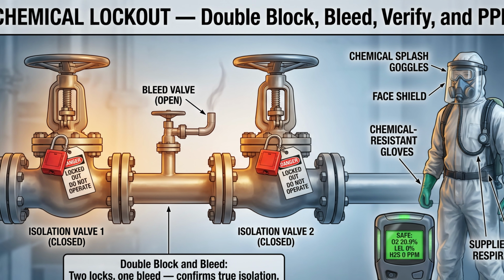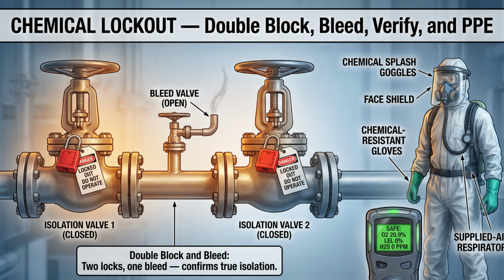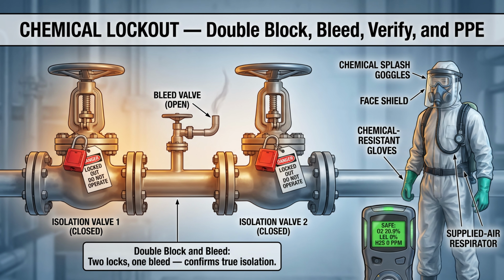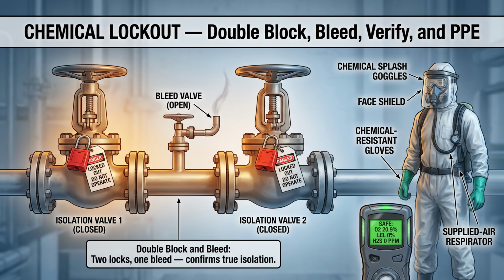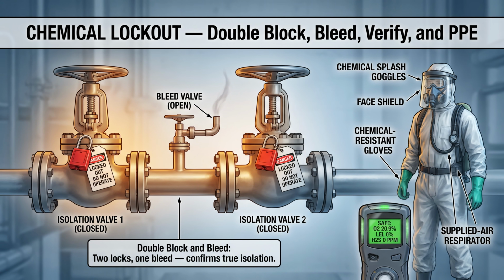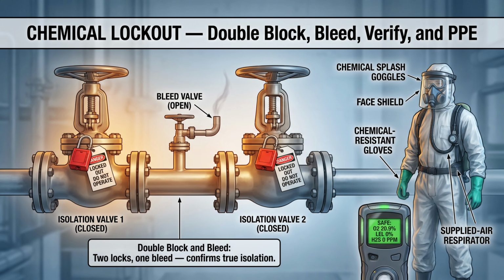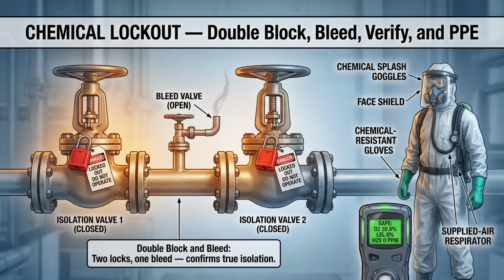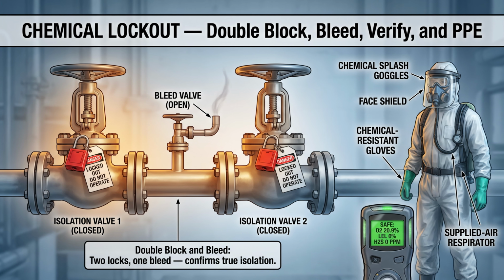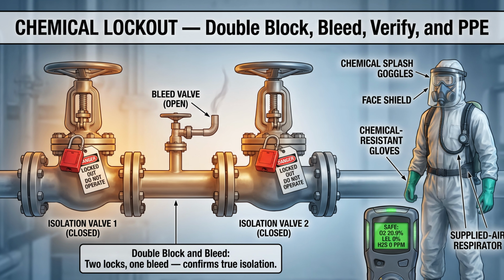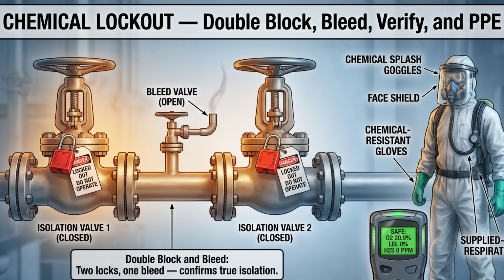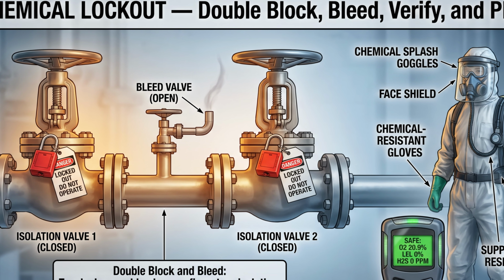Chemical energy control involves isolating chemical supply lines using lockable valves, depressurizing and draining lines before any work, and purging the system with inert gas or water flush as appropriate for the specific chemical involved. For high-hazard chemical lines, a double block and bleed configuration is commonly required. Two isolation valves with a bleed valve between them, confirming true isolation. Always don chemical-resistant PPE and confirm safe atmospheric conditions with air monitoring equipment before opening any chemical line.